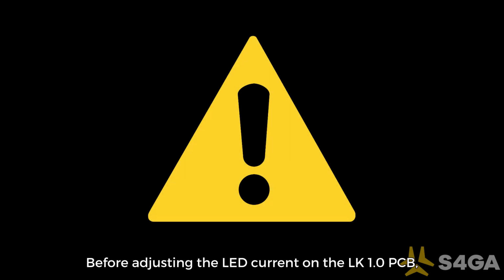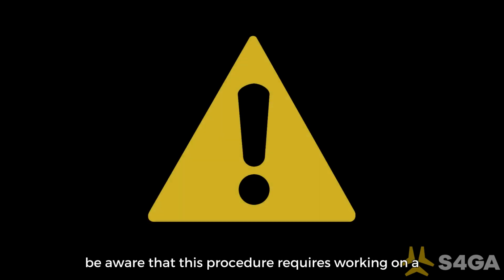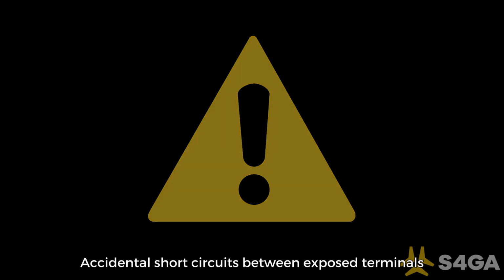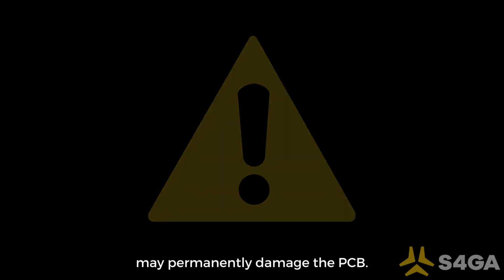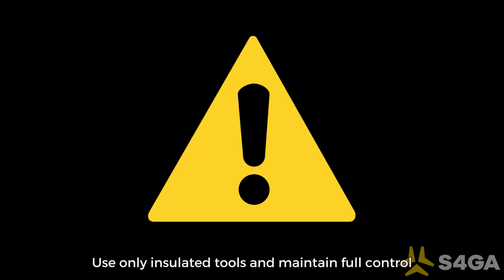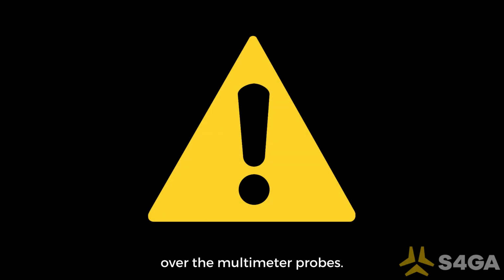Before adjusting the LED current on the LK1 PCB, be aware that this procedure requires working on a powered lamp. Accidental short circuits between exposed terminals may permanently damage the PCB. Use only insulated tools and maintain full control over the multimeter probes. Avoid touching adjacent components while performing live measurements.